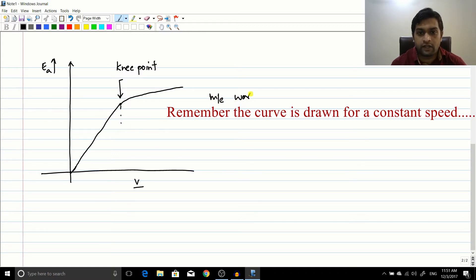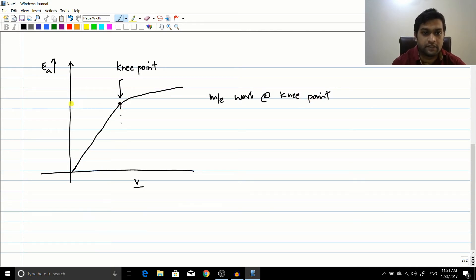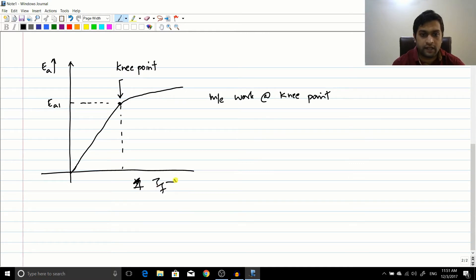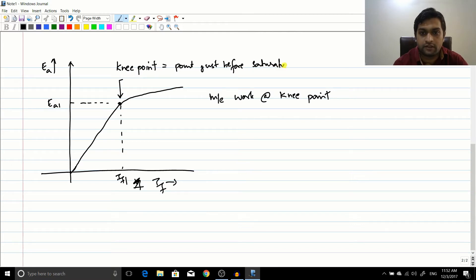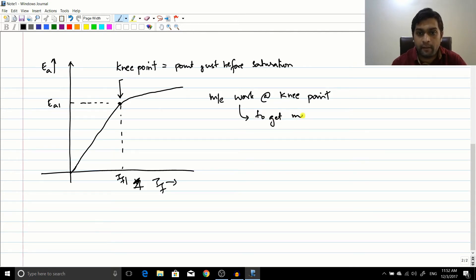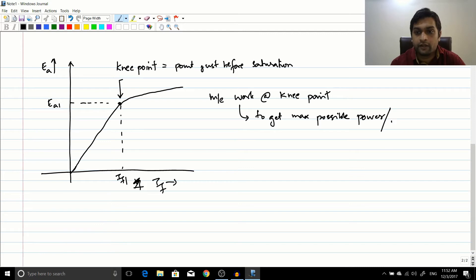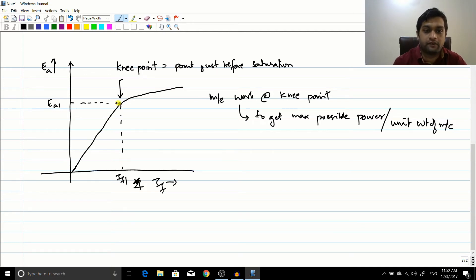If it is a generator it usually works here — this will be the EMF induced Ea1 for a particular field current IF. This is the point where usually the machine works. So what is the knee point? The knee point is the point just before saturation occurs. Now why does the machine work at the knee point? The reason is to get the maximum possible power per unit weight of the machine. To get maximum power per pound of the machine, you make it work near the knee point.